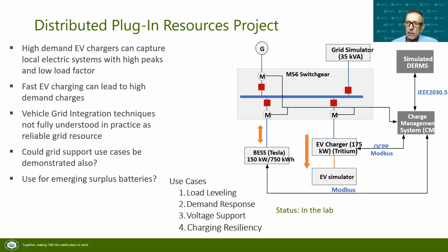What we've noticed over the years studying DC fast charging, individual chargers, as well as the association of chargers we call a charging plaza, is the load tends to be very spiky, like needle peaks if you look at the charge profile. From a utility perspective, you have to carve off a chunk of the grid to accommodate that peak power, but it may not last very long. Storage can even that out, and from a grid perspective, that allows us to maximize grid capacity for all customers.